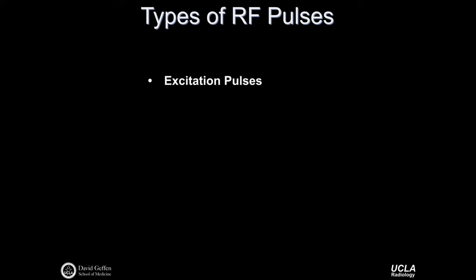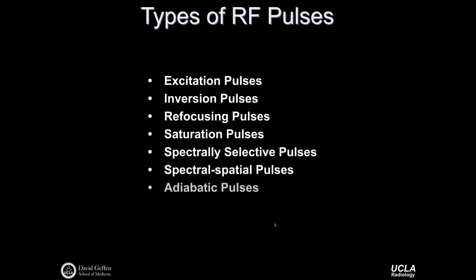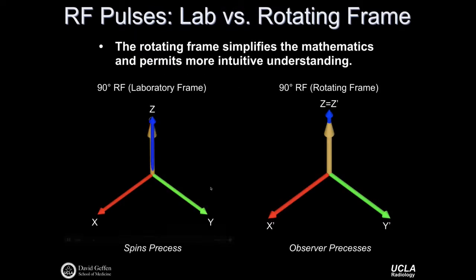There are many types of RF pulses: excitation pulses, inversion pulses, refocusing pulses, saturation pulses, spectrally selective pulses, spectrospatial pulses, adiabatic pulses, and more. This lecture series won't cover all possibilities, but excitation, inversion, and refocusing pulses are fundamental to MR. It's also important to recognize the distinction between the laboratory and the rotating frame. The rotating frame simplifies the mathematics and permits more intuitive understanding, which is why much of the mathematics of MR is performed in the rotating frame.